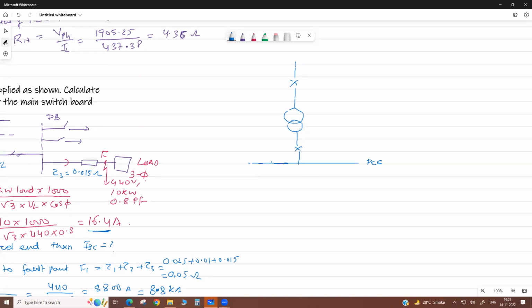Now this is a power control center. In the new system, it feeds your main distribution DBs, power control centers, like power and motor control center, MCC. So from here again the feeder goes to your area MCC. MCC means motor control center. Mainly motors are fed from this panel, okay. Motor loads, okay.